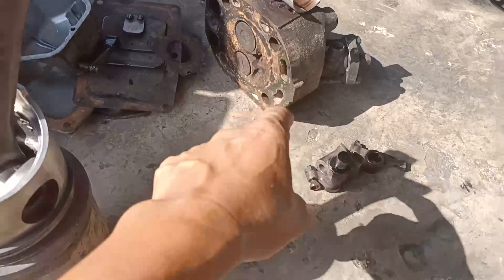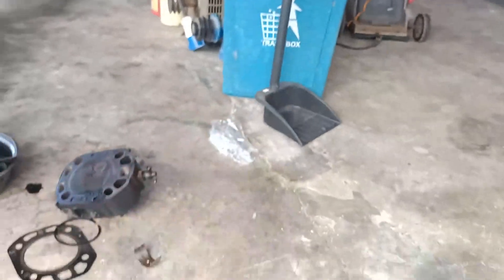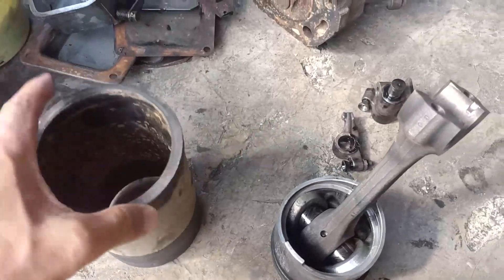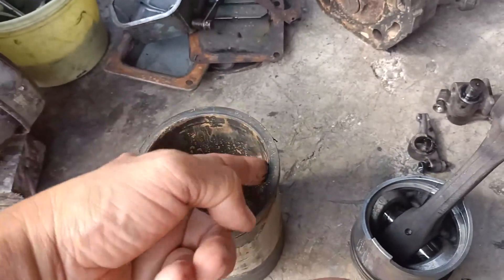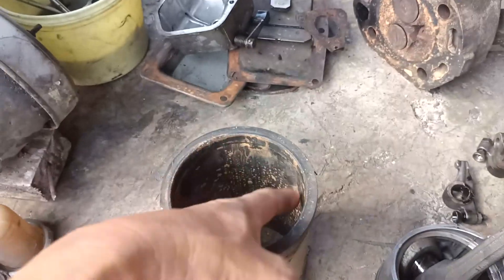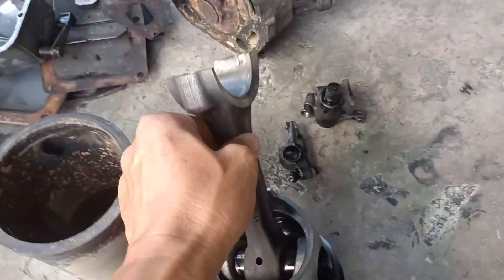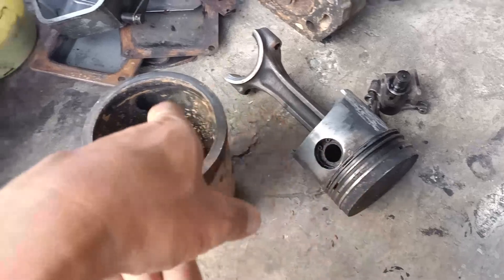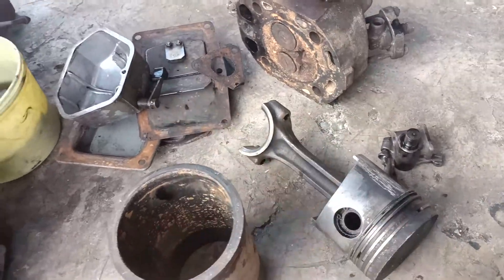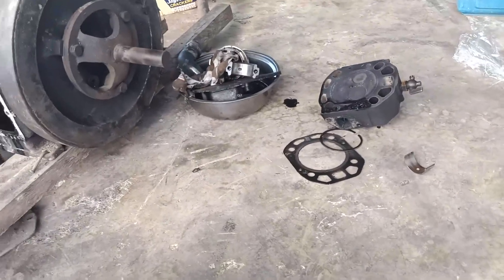This one is similar — bushing and oil again. As you can see, the bushing bearing is worn out from oil issues. Along with that, the liner needs to be replaced. There's a groove here because there's not enough oil, and then there's striation or scratches, so it will leak. What's going to be replaced: the piston, piston rings, and liner. The surfaces will also need to be re-surfaced.